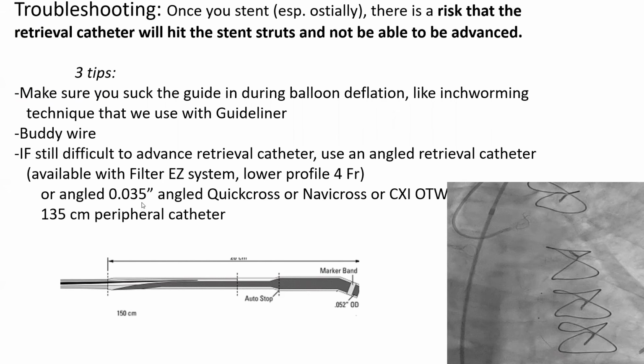The problem with those 0.035-inch peripheral catheters is that they are 135 centimeter over the wire system. So in order to use them with a Spider, you need to have kept your 300 centimeter Spider, not have broken it into 180 centimeter. You could also use them on a 180 centimeter Spider wire with a trapper if you have a 7 French guide. They won't fit with a trapper in a 6 French guide.